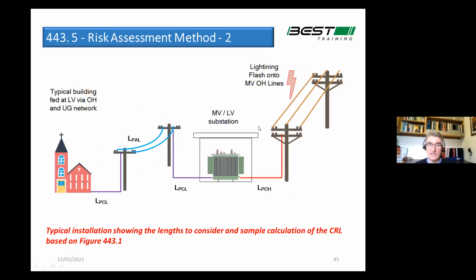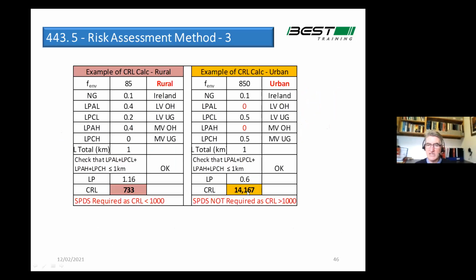And it gives you a diagram like that explaining the ratio of all the different cables, overhead high voltage, underground high, and so on. And then you carry out an assessment as I did there, simply in Excel, bang it in, and you see I got an answer here of 733 for a rural network, and a rural network obviously has more overhead lines on it, so it's more susceptible to lightning strikes, and it has a lower environmental factor to start off with. So it's nearly always, I would imagine, if you did any rural network, you're going to find it's mandatory to put them in, essential.